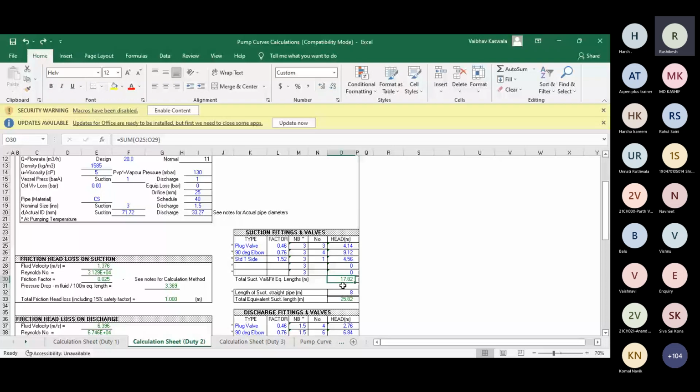It will give me the pressure drop same as that of a 10 meter of pipeline size of that particular suction line. अगर आपके suction line में एक globe valve है और suction line का size 3 इंच है, so that globe valve will give me equal amount of pressure drop which I will get from 3-inch line having 10 meter of length, right? Every line with respect to diameter and length will give me some pressure drop. So equivalent length of pipeline मतलब क्या है?